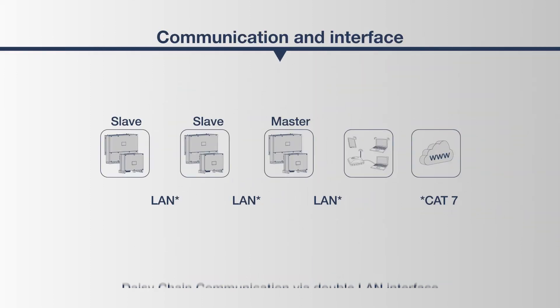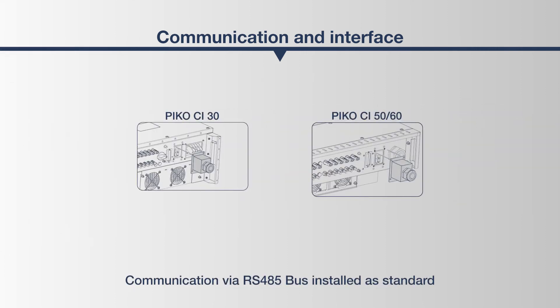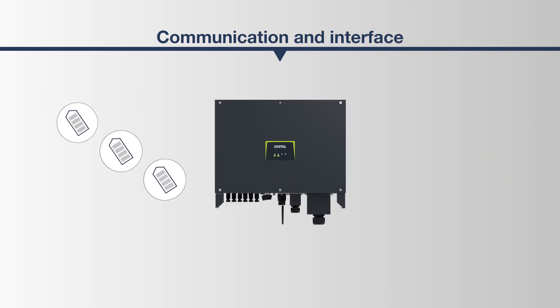As the heart of the photovoltaic system, the PIKO CI is optimally equipped in terms of communication. Using a double LAN interface implemented in the PIKO CI, a connection between several photovoltaic systems can be easily implemented in the sense of so-called daisy chain communication. An RS-485 interface is also installed as standard, which allows bidirectional transmission and the integration of up to 32 participants. In this way, the correct information is always sent to the correct recipient at the correct time.